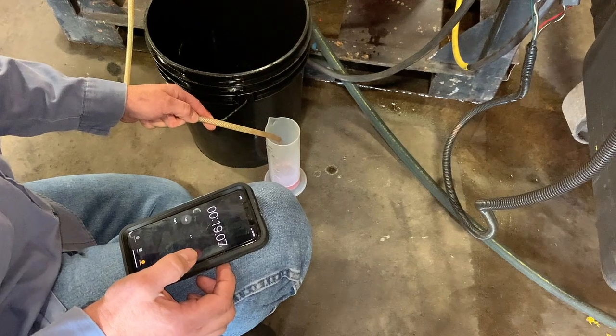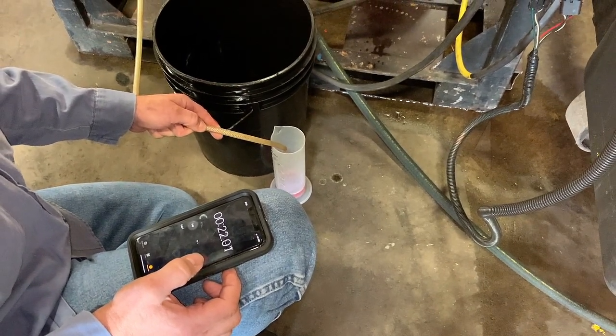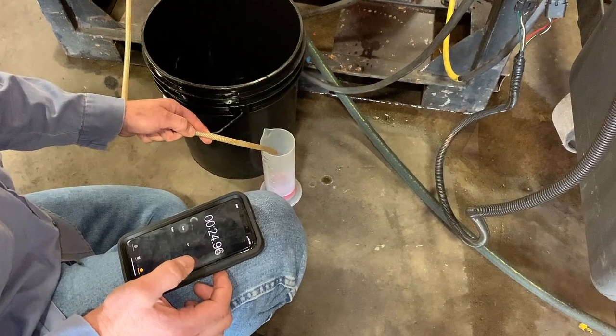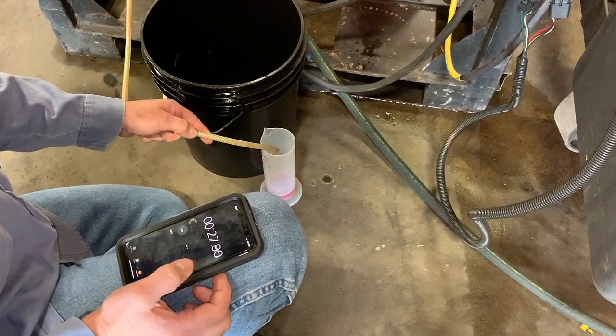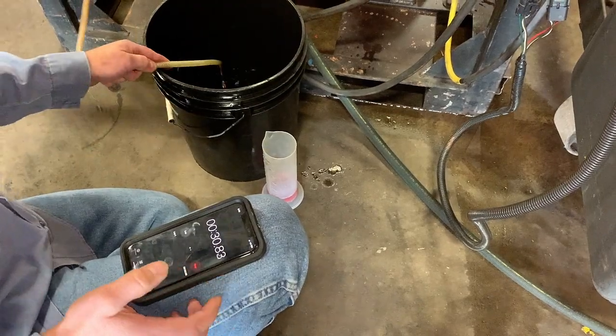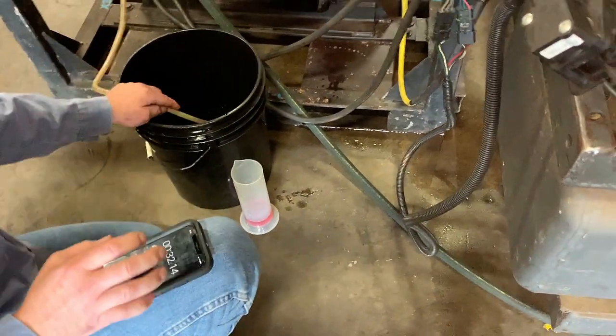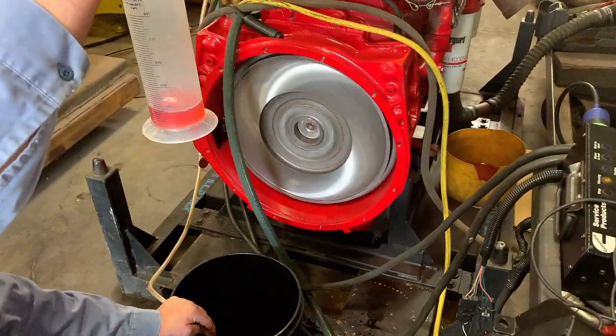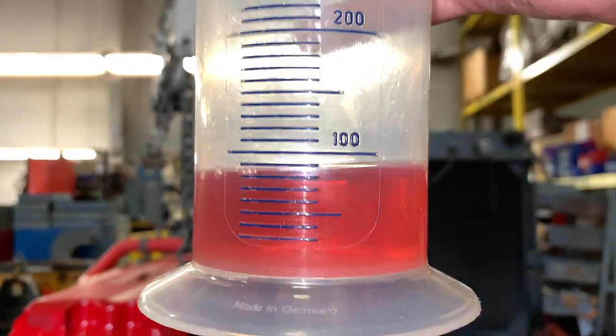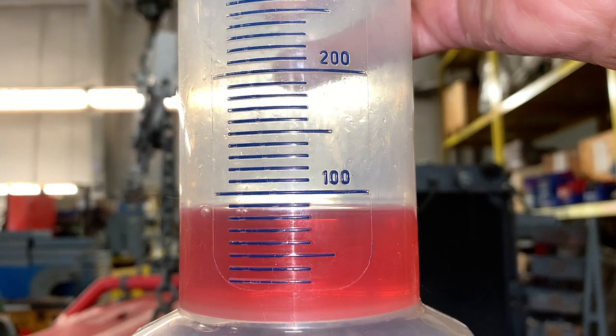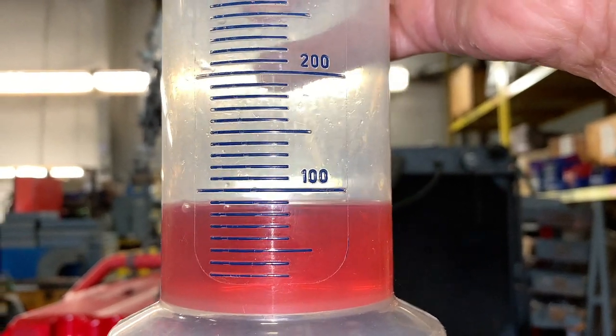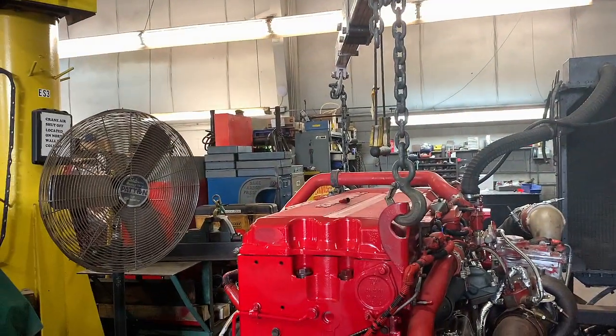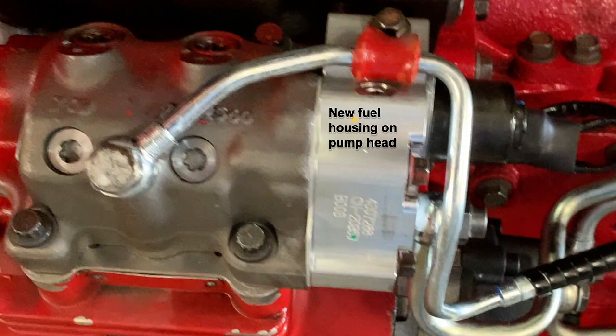And if we're not inside of those limits, then the directions and the tests that are found on QuickServe Online will tell us what we need to do. So here we are with our 30 seconds, and let's take a look and see how much fuel we have in that container. And we have only about 90 milliliters, so we are about 35 milliliters shy. And by the way, we did this test three times in a row, and it came out about the same all three times.